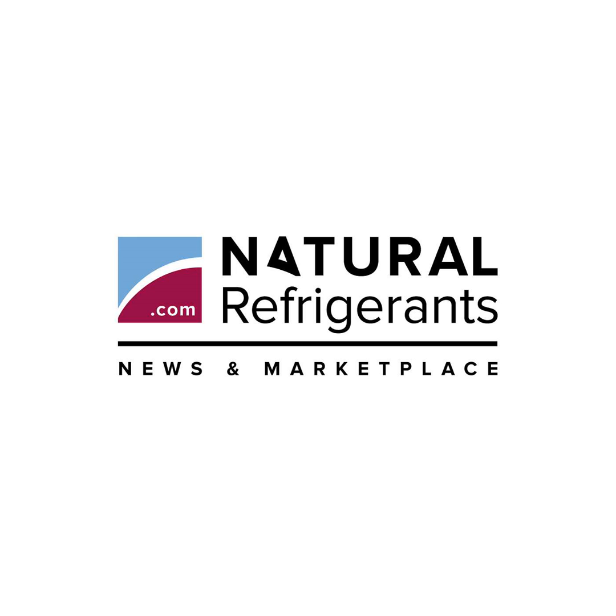Propane, Naturally Safe addresses the following questions. Is there a difference between heat pumps for commercial use and those for residential use? Are small charge quantities exempt from risk assessment? Is it unnecessary to prepare an explosion protection document for heat pumps? Does a hermetically sealed refrigerant circuit mean that no Ex-certified, explosion-proof equipment is required? Does ventilation mean that Ex-certified equipment is not required? Why is it problematic to use semi-hermetic compressors without EX certification, even if they are tight? Are possible and potential ignition sources exactly the same? Is there any legal requirement for ventilation of cargo compartments in service vehicles?